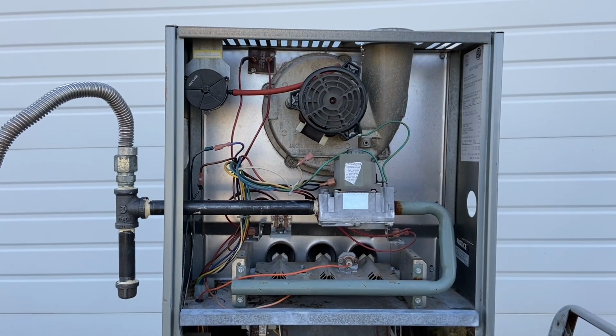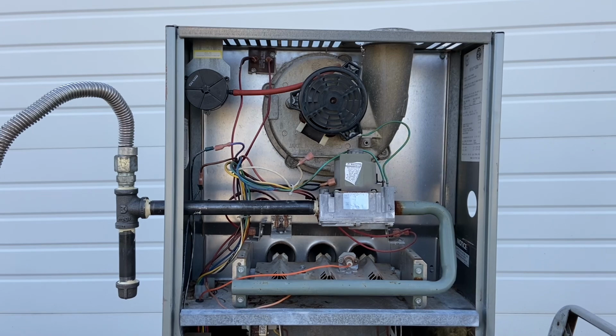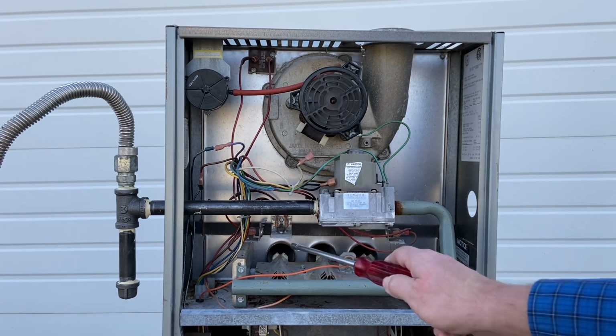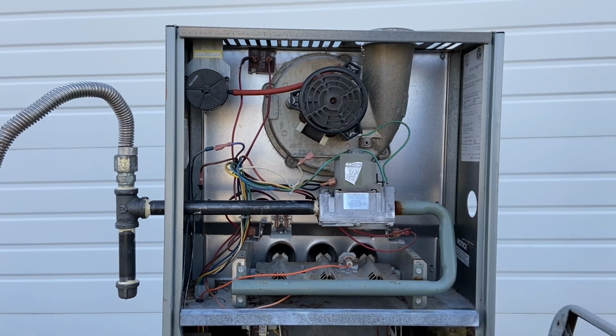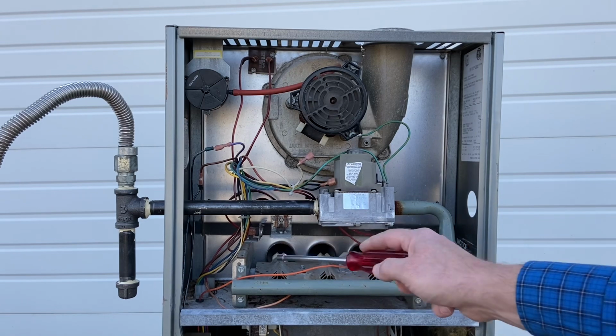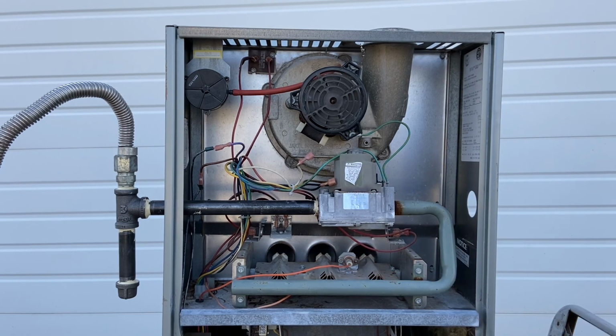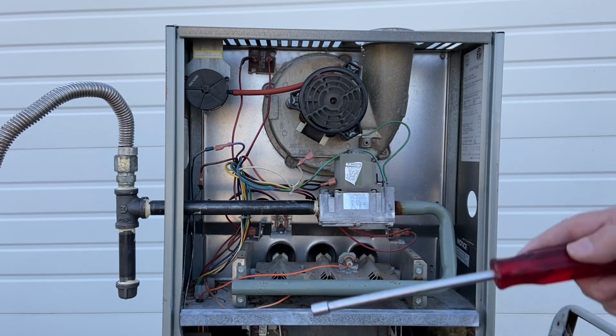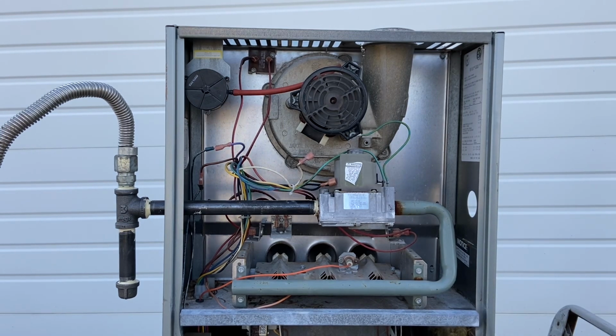And 2 of the 3 had tripped. But before they tripped, we still had a lot of scarring going on. I've heard people say, hey, it's okay to bypass that safety just for a little while because there's other safeties on there. And it's simply not true. These other safeties are there, but by the time these safeties tripped, it was already too late for this furnace. So you don't want to rely on just one safety. You don't want to bypass any safeties at all. They're all there for a reason. Never bypass a safety. They're designed to keep the customer safe, you safe, everybody safe.